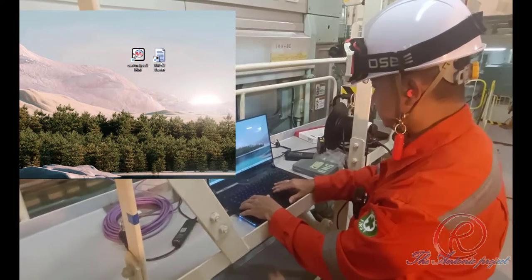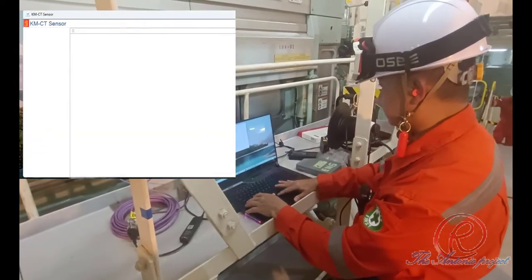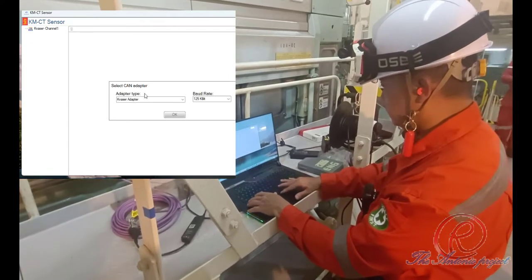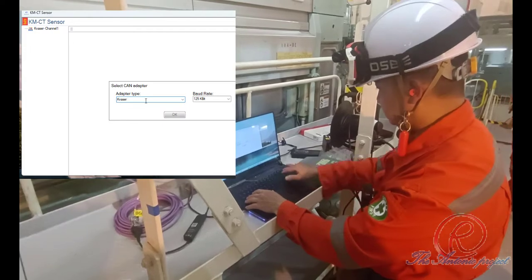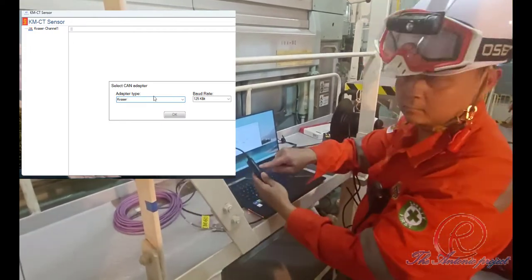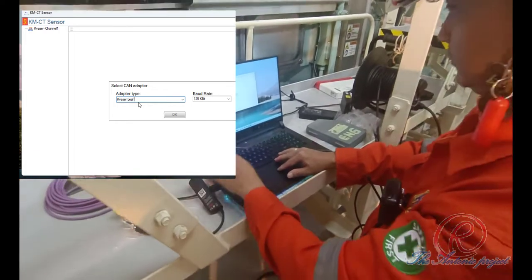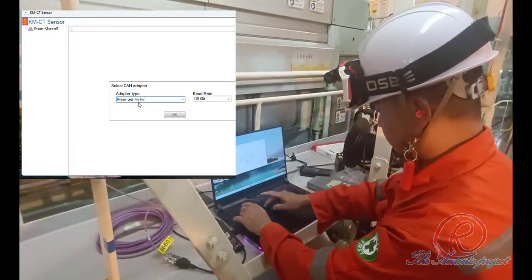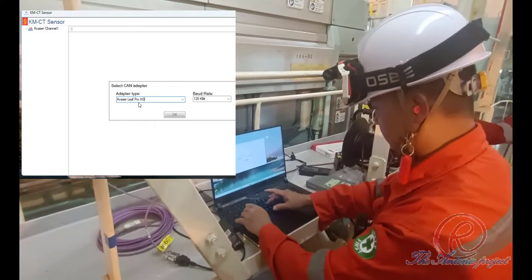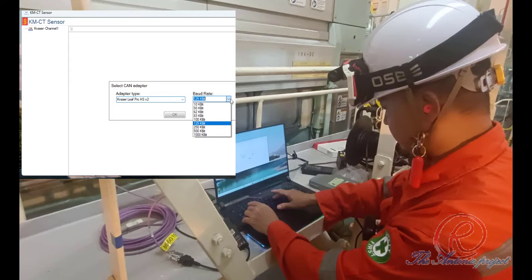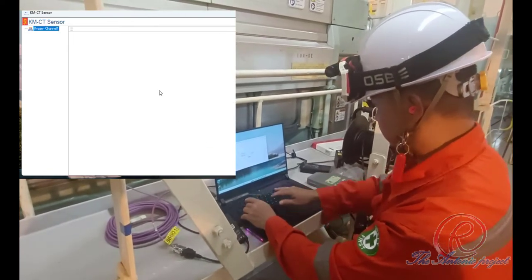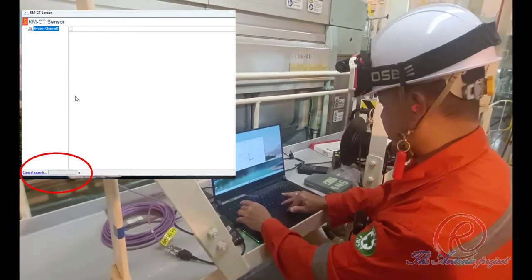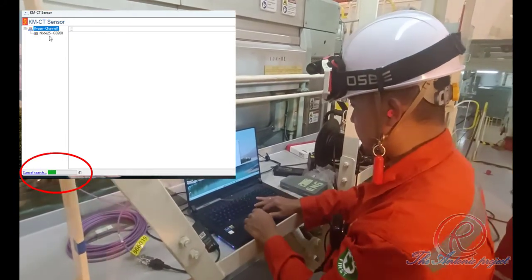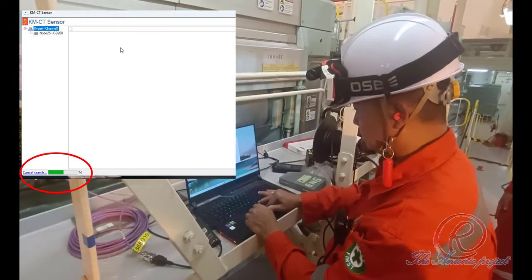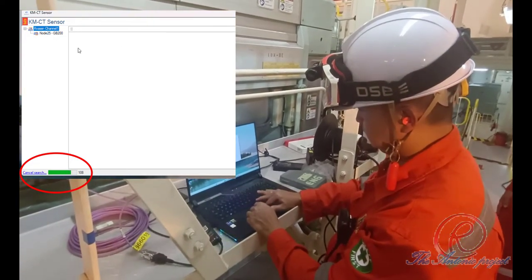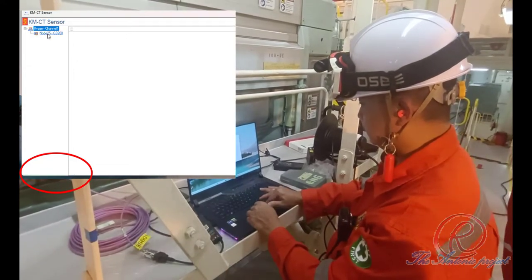1. Start the KMCT tools. Make sure that the KMCT version is 5.2.0.9 or newer. Select Add CANopen from the upper left corner of the screen. Input the adapter type Kvaser Leaf Pro HS v2, then click the drop down list for baud rate, then choose 500 kilobit. Right click on the Kvaser channel on the left and choose search nodes. The node search is displayed on the bottom left corner until 128 nodes have been run through.